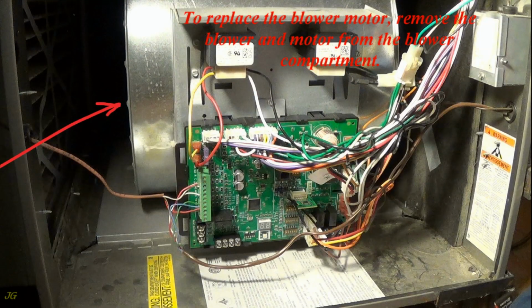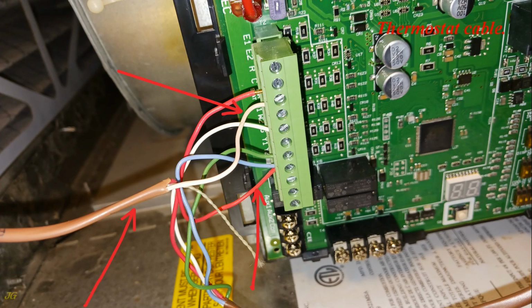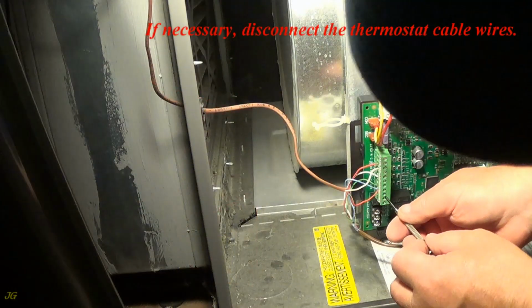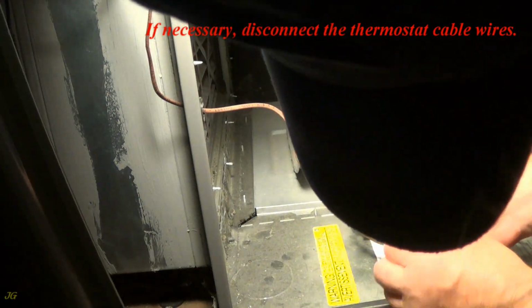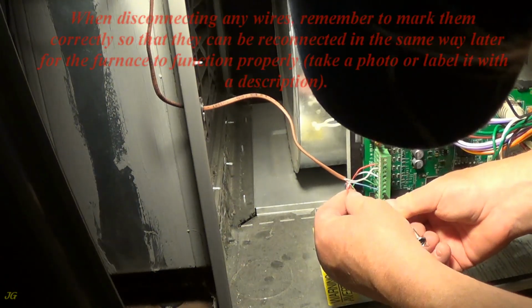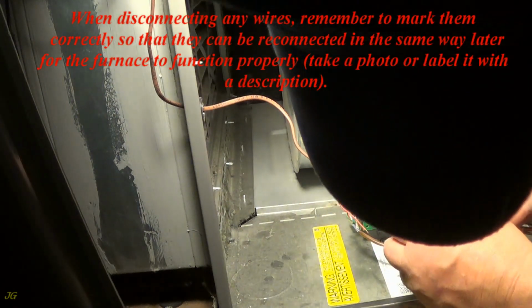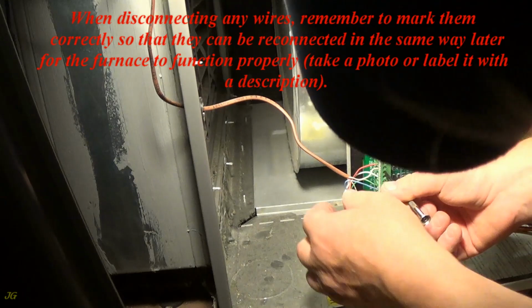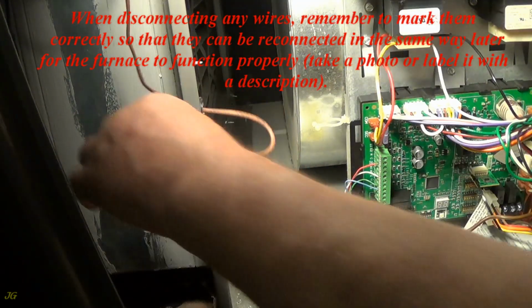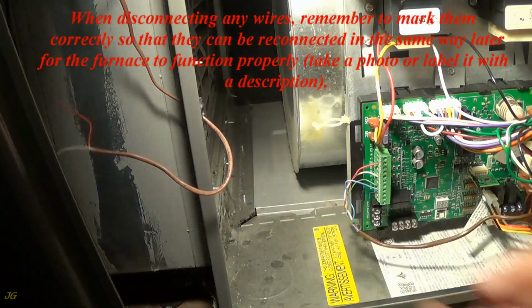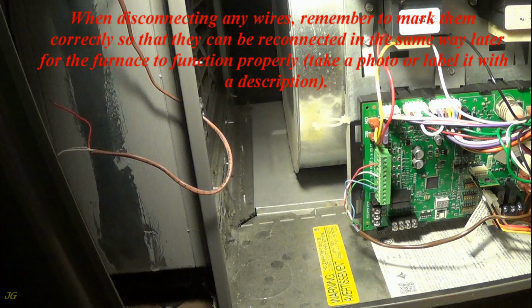To replace the blower motor, remove the blower and motor from the blower compartment. Thermostat cable. If necessary, disconnect the thermostat cable wires. When disconnecting any wires, remember to mark them correctly so that they can be reconnected in the same way later for the furnace to function properly. Take a photo or label it with a description.